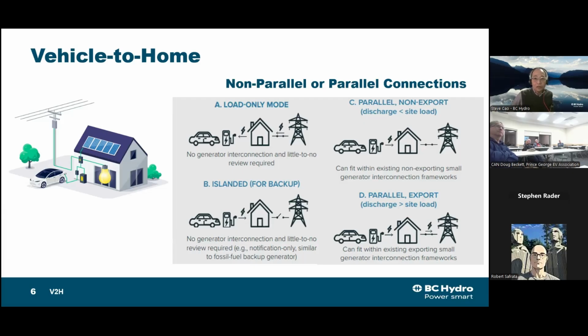So all the considerations related to circuits and panels apply to case C just like case B. But because you're doing a parallel connection, BC Hydro approval is going to be required, most likely, because there are additional safety measures needed since the grid is expected to be live and operating in parallel with the battery discharge when that happens. So the review process should be expedited if you don't have any injection into the grid.